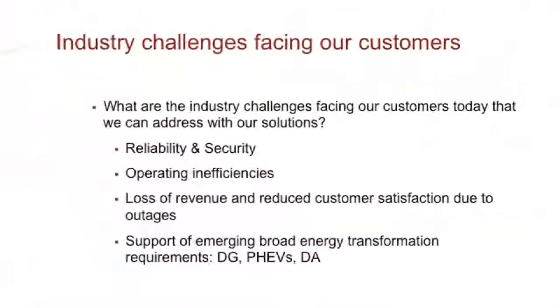And when I talk about distribution automation, I'm talking about self-healing grids. So that's going to be a little bit more of the focus today. Fault detection, isolation, restoration schemes, automatically reconfiguring the system, isolating the faults. But also you have volt-var optimization. Some of you might have already seen some of the products that help you with volt-var optimization, CVR, conservation voltage regulation, and so on. So that's kind of where the recloser fits in on the distribution automation side. So basically that's the next phase of smart grid deployment, and in that trend, this is where the recloser fits.